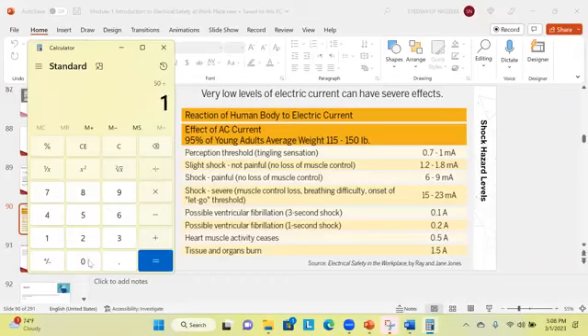For example, if the body is wet and the human body resistance has reduced to 10,000 ohms, multiply by 100. So that will be around 50 divided by... I am multiplying it by 50 volt. We'll keep 10,000. Sorry. So it will be around 5 milliampere.